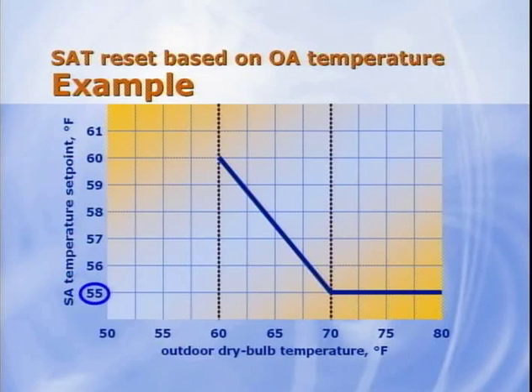Finally, when the outdoor temperature is colder than 60 degrees, no further reset occurs, and the supply air set point remains at 60 degrees Fahrenheit. Limiting the amount of reset to 60 degrees allows the system to satisfy cooling loads in interior zones without needing to substantially oversize VAV terminal units and ductwork.